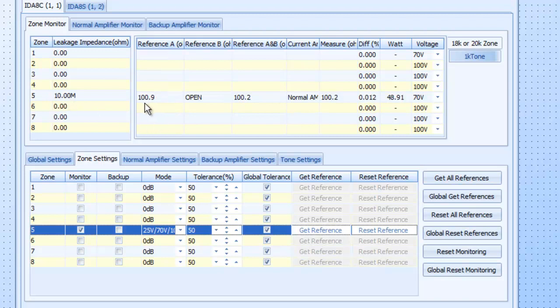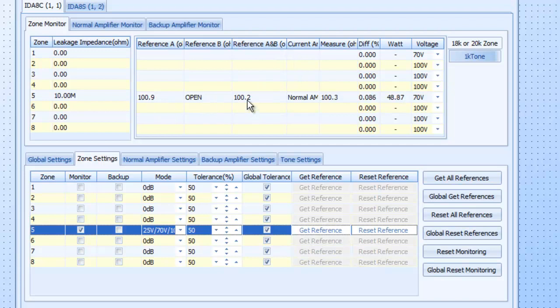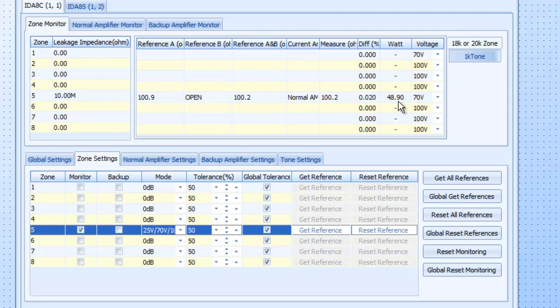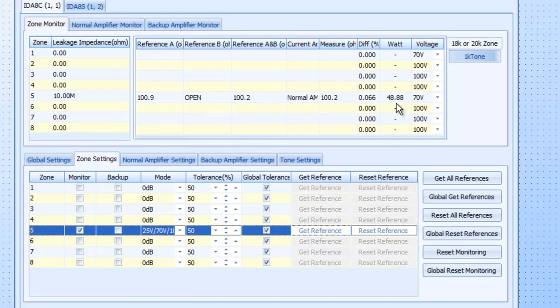My reference A is 100.9 ohms. I have nothing hooked to my line B output on zone five. And the reference between these two is the same, obviously. And it's on the normal amp. That's the measurement. And the differences is in the hundredths and thousandths of a percent. And the wattage that it's looking at at 70 volt is 48.85. And it's a 40 watt speaker. And it says it's about 48 watts, which is about right.